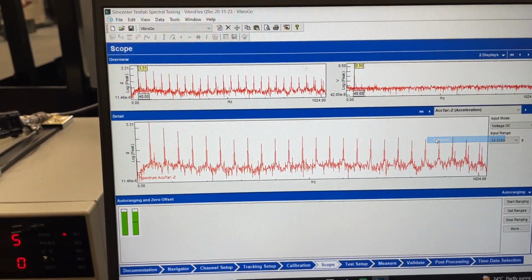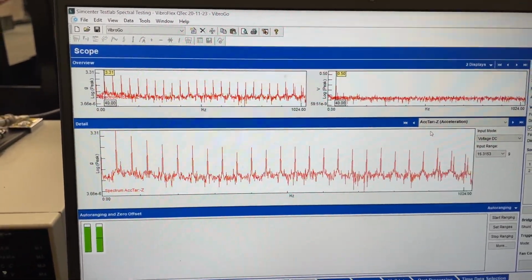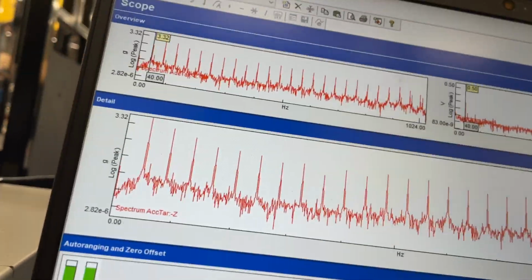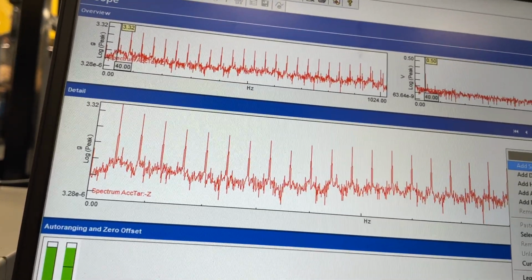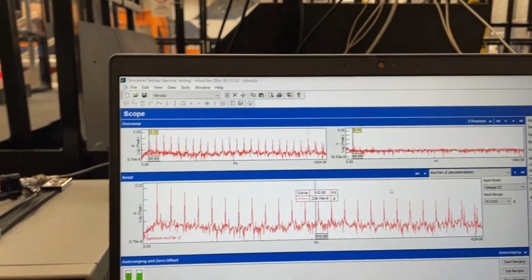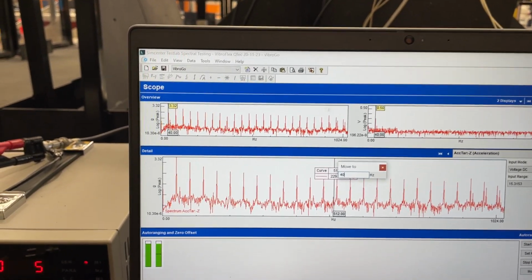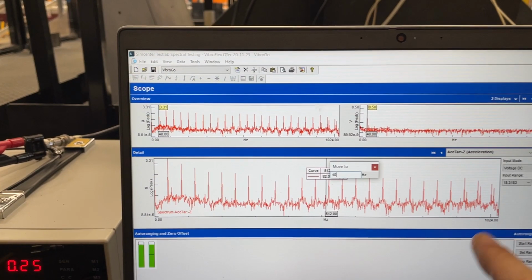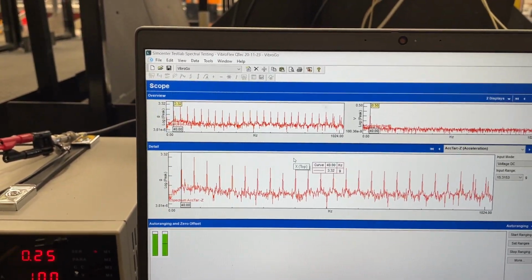We expect a little bit of a square profile, not perfectly sinusoidal. It's a mechanical system, so we expect a few harmonics, but not such a horrible looking curve that we have such high level harmonics at the first, second, third harmonic, travelling all the way up the spectrum, which indicates a very square looking sine wave.